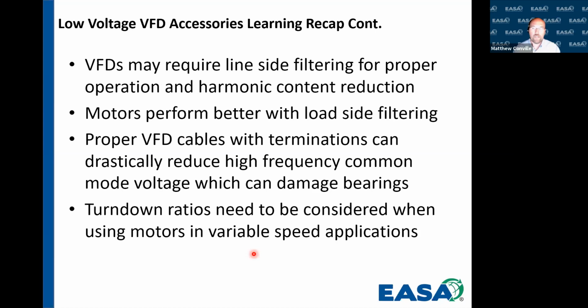Variable frequency drives, depending on their topology, may require line side filtering for proper operation and reduction of harmonic content, especially if we have multiple drives on the same line. Motors just perform better with load side filtering. And the reason for that is it's closer to a sine wave. We're reducing that rate of rise and we're reducing those peaks. Proper VFD cables with terminations can actually reduce high frequency common mode voltage. And that's a second way that we can cause bearing damage or fluting.